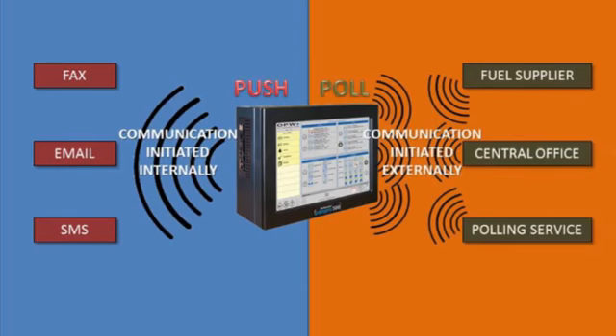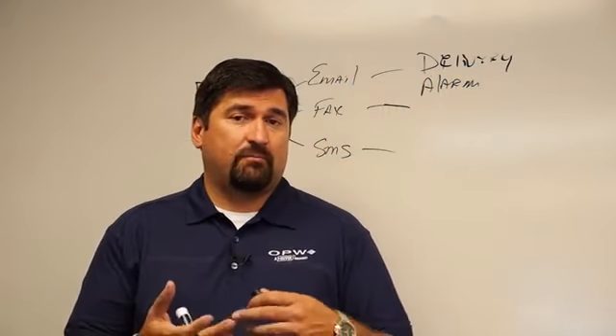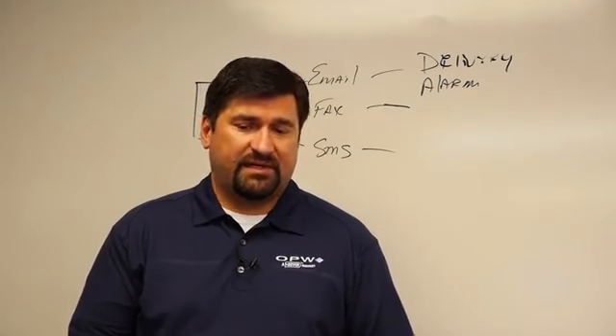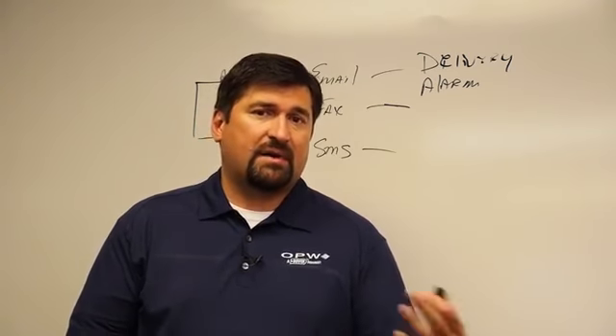Most gauges, if they have an optional modem or a TCP/IP connection in there, third-party polling companies are able to come in and interrogate the gauge, and they're polling for inventory, delivery, high water, low product, sensor statuses, whether you run tank tests, line tests. They're interrogating the gauge, and they're taking that information and storing it, but they're also supplying it out to the companies that need it, whether you have a contract with a delivery company to supply you fuel, or a contract with a maintenance company that if you have fuel in an STP sump or underneath the dispenser pan, they'll automatically dispatch that company out to take care of that service for you.